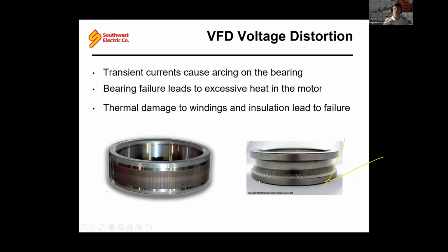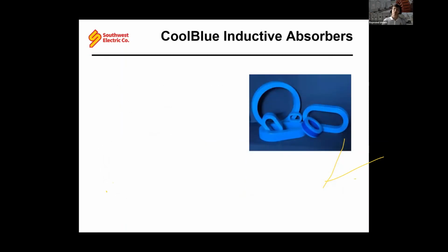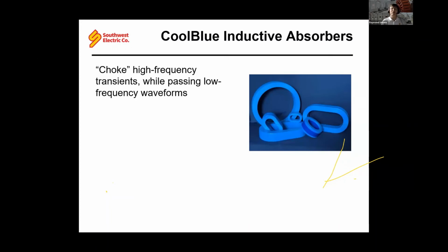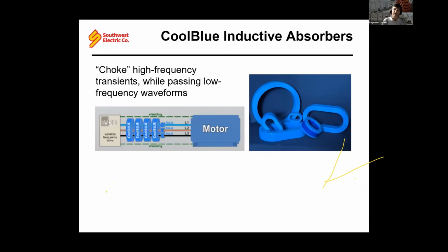So this is going to shorten the life, definitely, of the bearing. And if you shorten the life of the bearing, you almost always end up shortening the life of the motor, from these transient currents. What we would highly recommend, and we do this for all of our customers, is a method of filtering out those high frequencies in order to keep that damaging current from even entering the motor. So in your supply line between your VFD and your motor, you would put what we call, well, there's a manufacturing company that provides this.